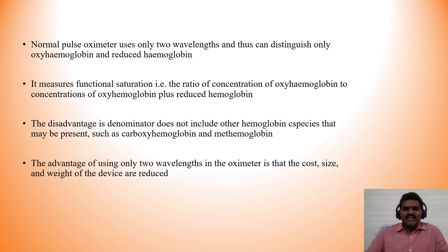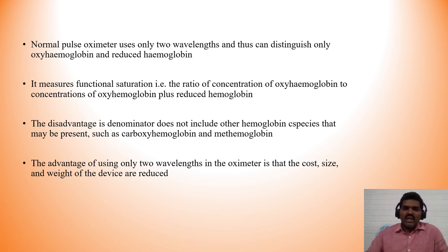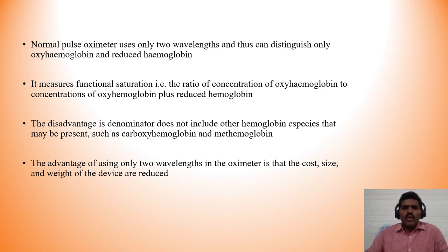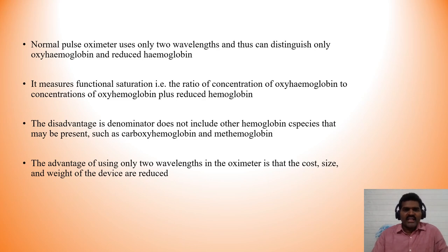The advantage of using only two wavelengths is that the cost, size, and weight of the device are reduced. Other instruments like co-oximeters use more wavelengths to differentiate between different hemoglobin species — that is the principle used for measuring methemoglobin and carboxyhemoglobin when those conditions are clinically suspected.